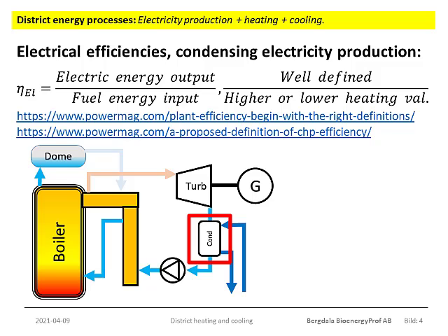So following the turbine is a condenser, and to this condenser is fed cooling water. This water may come from a lake or from a river or from a cooling tower or from the sea or something. The colder the cooling water, the better. The condensed steam, the condensate from the condenser, now has a low pressure and a low temperature, maybe 10 degrees Celsius and a mere fraction of atmospheric pressure.